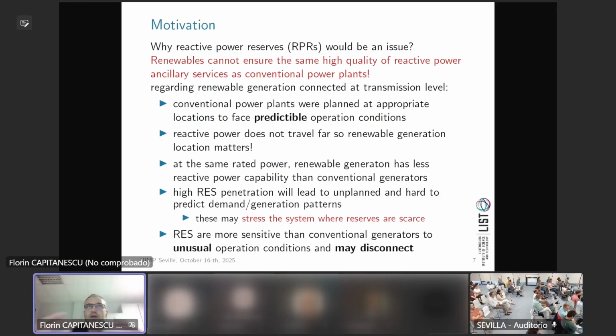So it's very, very important how we plan that. Another thing is, if you take, at the same rated power, a conventional generator and let's say an inverter based resource, you will see that they are constructed in a way in which their capability is actually smaller, and quite smaller, especially in absorption mode. So neither production nor absorption of reactive power.